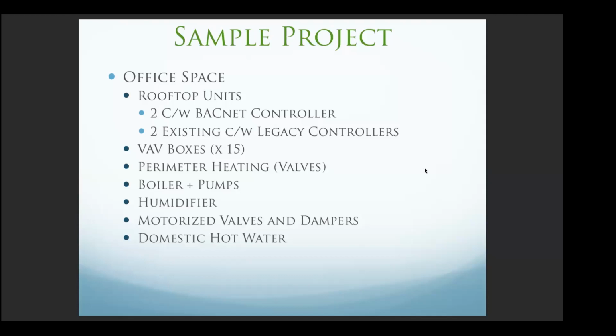A bunch of the manufacturers have started moving towards IP-based systems. So their controllers are completely IP-based, BACnet over IP. So they're doing all their projects that way. I wouldn't say it is significantly more or less. I hate to say this answer, but it really depends on the project and how long you have to do the runs, etc. So it would go by project basis in terms of cost, because that would come to the electrical subcontractor that the controls contractors typically hire to do all the wiring in the project, and they would be the ones running the Cat5 cables around the building.